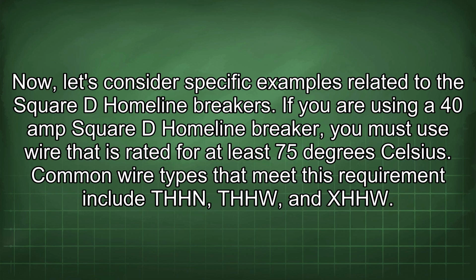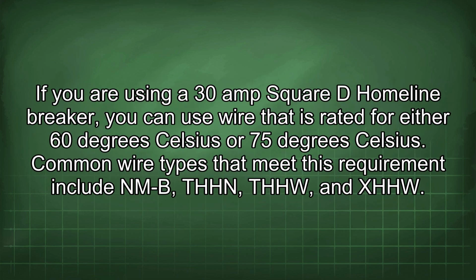If you are using a 40 amp Square D Homeline breaker, you must use wire that is rated for at least 75 degrees Celsius. Common wire types that meet this requirement include THHN, THHW, and XHHW. If you are using a 30 amp Square D Homeline breaker, you can use wire that is rated for either 60 degrees Celsius or 75 degrees Celsius. Common wire types that meet this requirement include NMB, THHN, THHW, and XHHW.